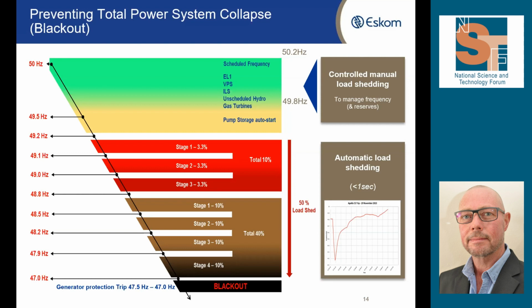If we go any deeper than that, at 48.8 hertz, we start to do much bigger blocks. And we have then 4 blocks of 10% each, so really large chunks of load that would come off. And that would start tripping between 48.8 hertz all the way down to 47 hertz. In total, we've got about 50% of the load on the power system connected to this system. And so within literally less than a second, we could disconnect 50% of the power system.